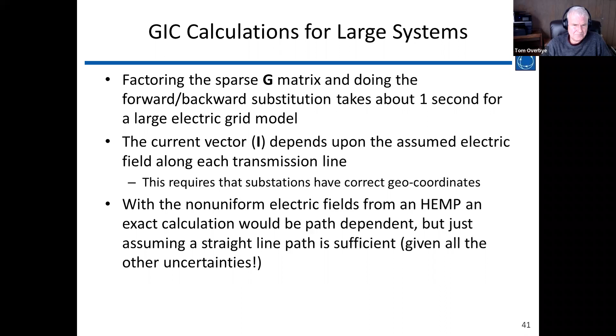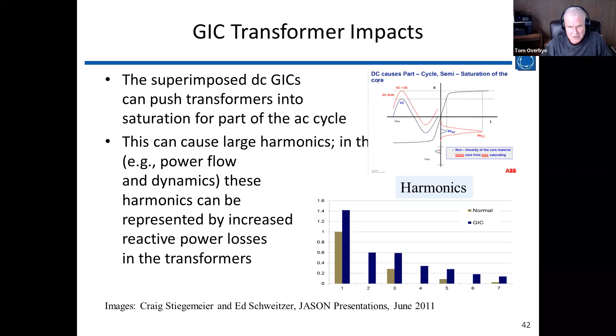How do GICs impact the transformers? Increased reactive power losses cause harmonics, and those harmonics cause potential heating and potential voltage collapse. The question is how do they impact the transformers? The same way GICs from a GMD would impact transformers. A lot of people use a linear model that says if you have so many GICs in a transformer, it maps into so much reactive power loss.